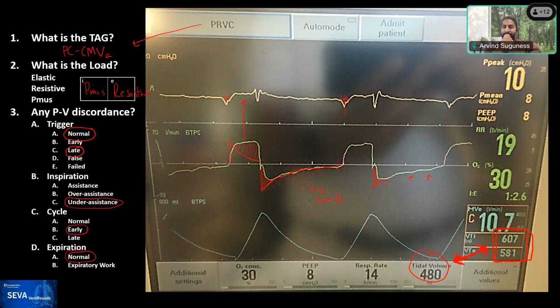He says, if PRVC on the Maquet is similar to AutoFlow on a Dräger, then the inspiratory flow assistance stopped as soon as the set VT was reached while the patient was still actively inhaling. So PRVC on the Maquet is the same. They both have the same mode tag as AutoFlow on a Dräger. But the inspiratory period lasts as long as it is set, so it lasts for the entire I time. It doesn't end just because they reach the set tidal volume, which is why this patient is receiving a larger tidal volume than the set one. Yeah, that's correct.